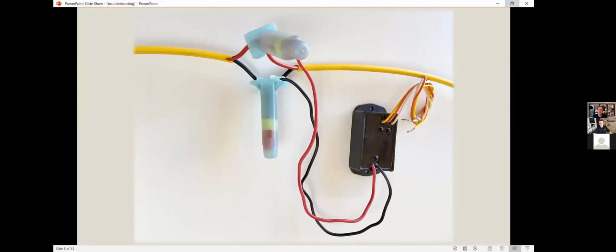So we might see a solenoid open or a solenoid short, and that would not be a two-wire issue. For example, right now there is no solenoid hooked to this device. If it tries to turn this on and look for a solenoid, it's going to look for 20, 30 ohms of resistance, won't find it and say there's a missing solenoid, and throw an error. If the solenoid is shorted or has a corroded connection, it would also throw an error. Those are the other common ones.